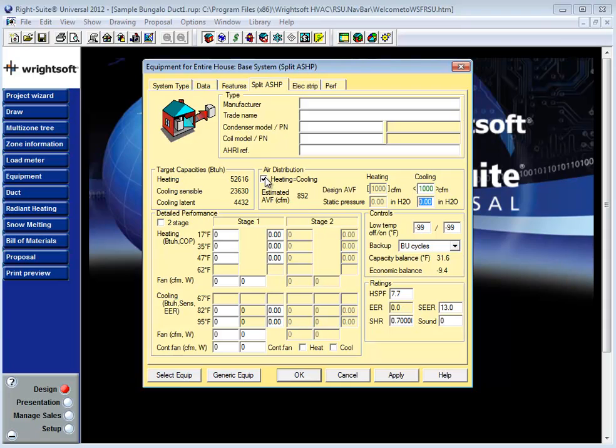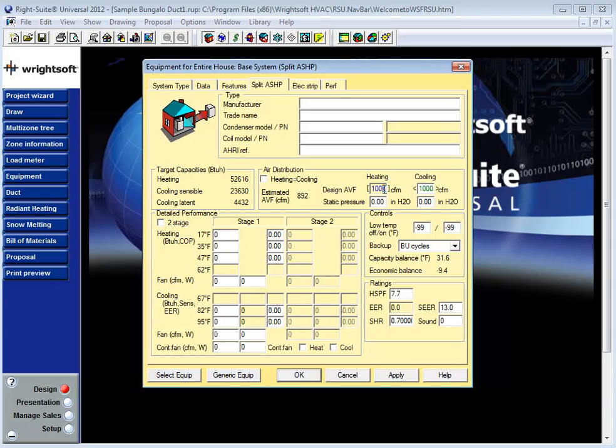If you want to adjust individual heating and cooling airflow needs simply uncheck this box. You can then manually adjust both the heating and cooling CFM and static pressure numbers separately. This can be useful for situations where seasonal balancing is attainable and in situations where you want to base your design on one over the other. For the purposes of our videos here we're going to use a heating equals cooling design option.